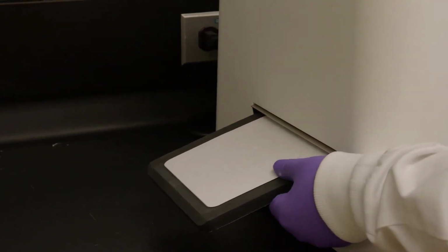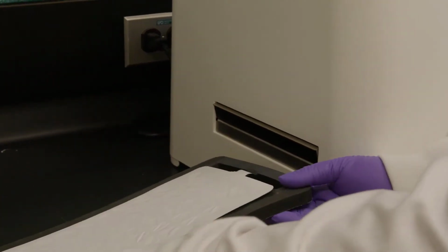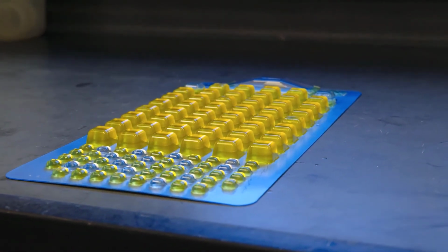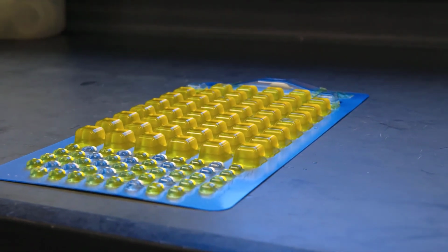So after we take the plates out after about 24 hours, we essentially just count how many wells we see a color change in, and then we look up those numbers on a reference table to determine the most probable number of fecal coliform or enterococci in that sample that we took. So within minutes of taking the sample out of the incubator, we know whether we're having a permit exceedance. And if we do have a permit exceedance, we're able to report that very quickly to our shellfish authorities.